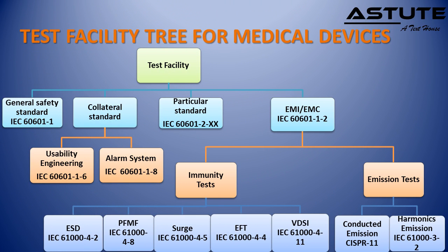Test facilities for medical devices, with respect to the standards, are shown in this tree diagram. There are main four types of testing facilities that are General Safety Standard, as per 60601. It focus on safety of the equipment, users or patients, related to electrical safety, mechanical safety, and physical safety testing, etc. We also conduct testing as per the collateral standards, for example usability engineering and alarm system. We also conduct testing as per the particular standards, for example testing of X-ray machines, testing of syringe pumps, and testing of ECG machines, and phototherapy equipments, etc.